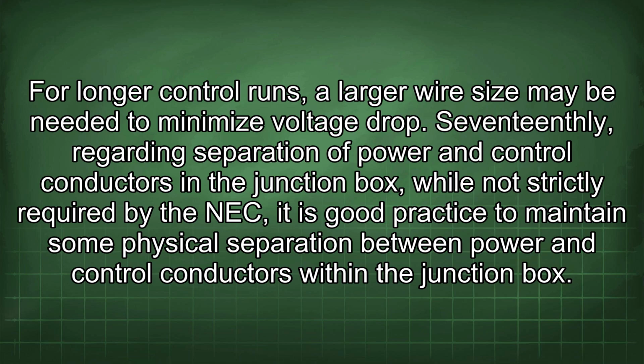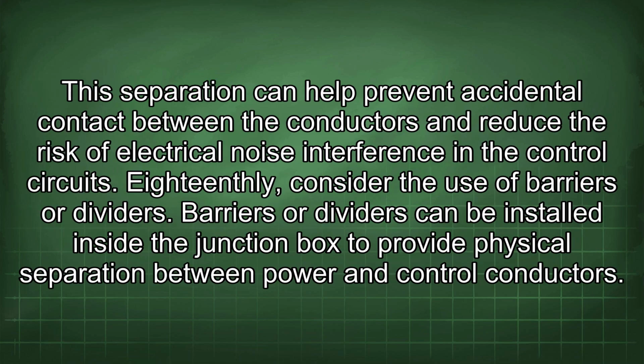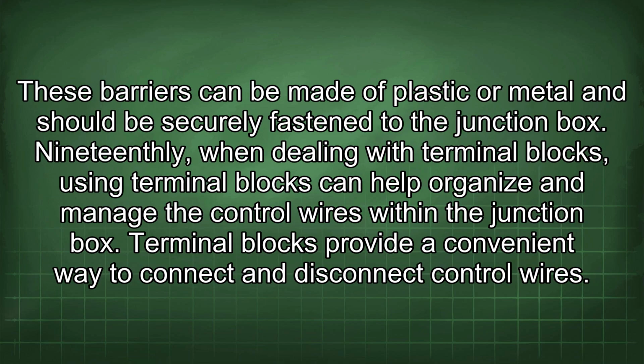17thly, regarding separation of power and control conductors in the junction box, while not strictly required by the NEC, it is good practice to maintain some physical separation between power and control conductors within the junction box. This separation can help prevent accidental contact between the conductors and reduce the risk of electrical noise interference in the control circuits. 18thly, consider the use of barriers or dividers. Barriers or dividers can be installed inside the junction box to provide physical separation between power and control conductors. These barriers can be made of plastic or metal and should be securely fastened to the junction box.